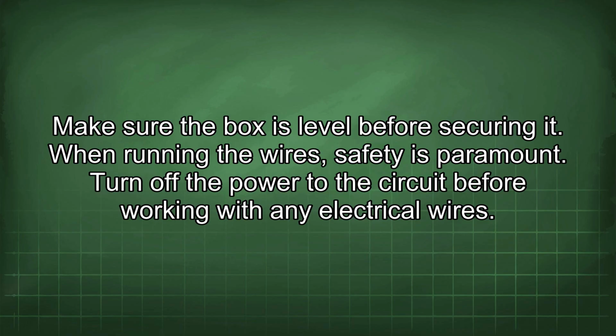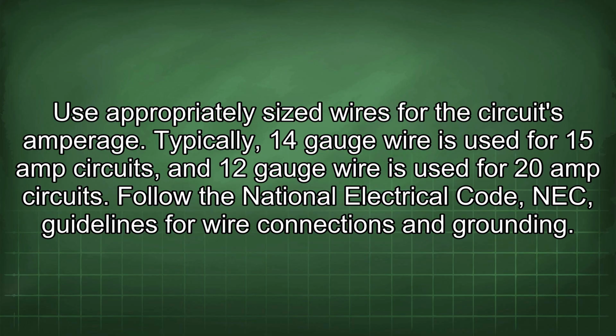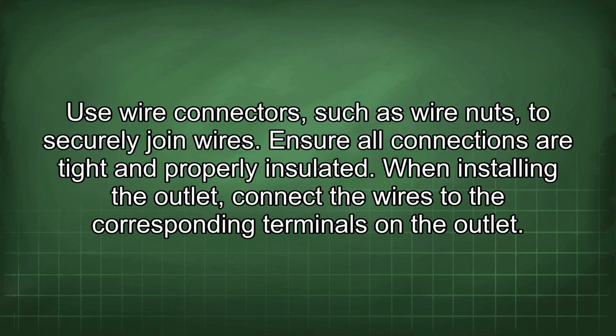When running the wires, safety is paramount. Turn off the power to the circuit before working with any electrical wires. Use appropriately sized wires for the circuit's amperage. Typically, 14-gauge wire is used for 15-amp circuits and 12-gauge wire is used for 20-amp circuits. Follow the National Electrical Code (NEC) guidelines for wire connections and grounding. Use wire connectors, such as wire nuts, to securely join wires. Ensure all connections are tight and properly insulated.